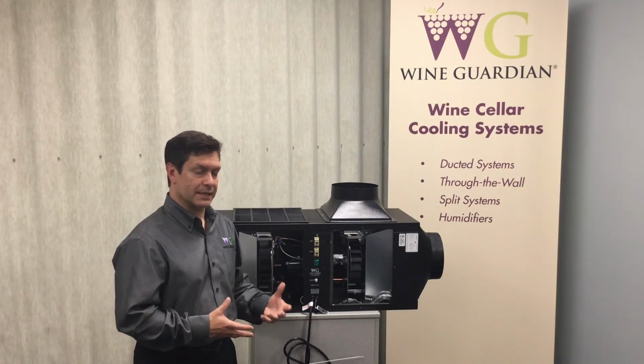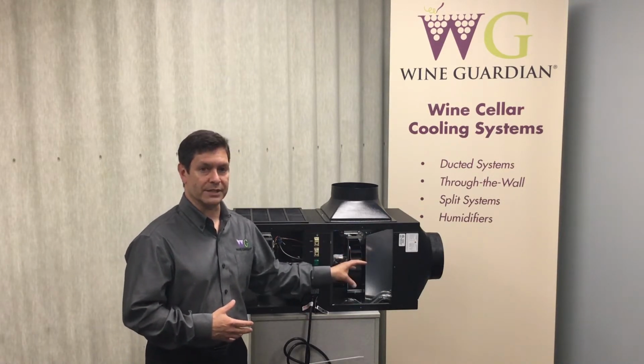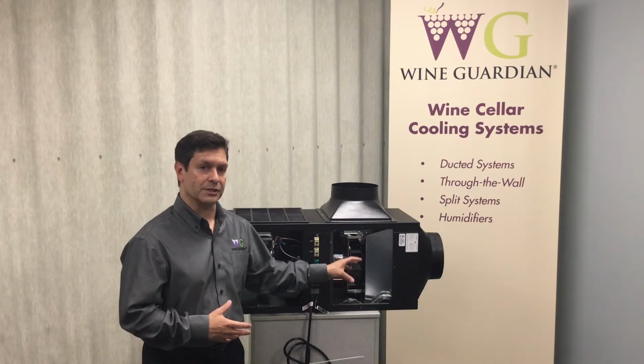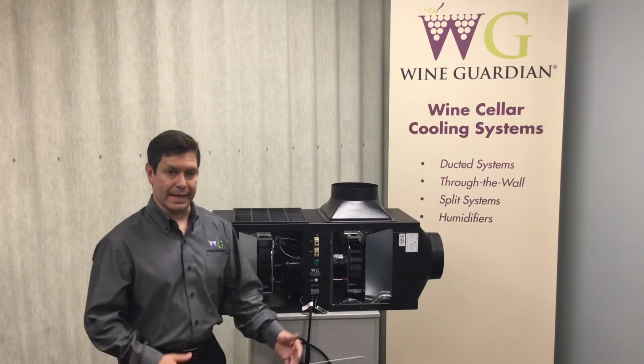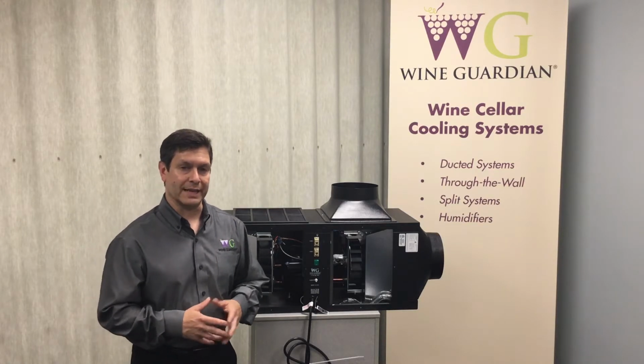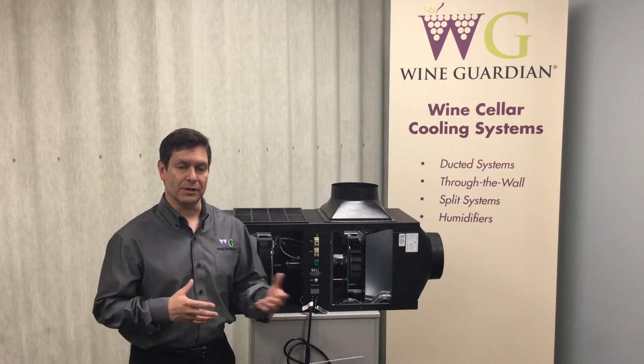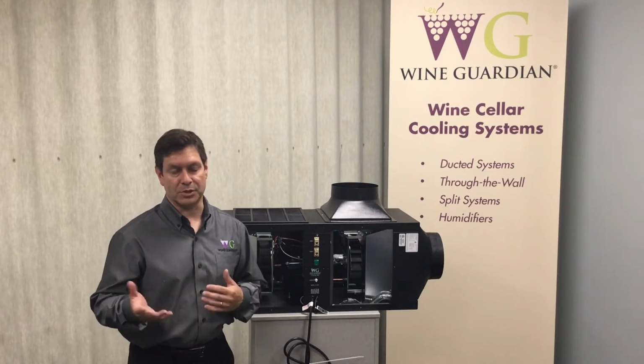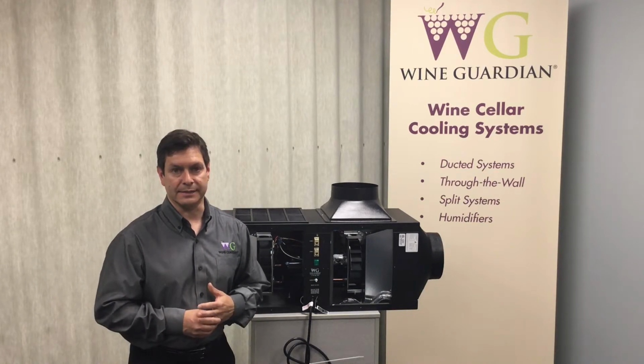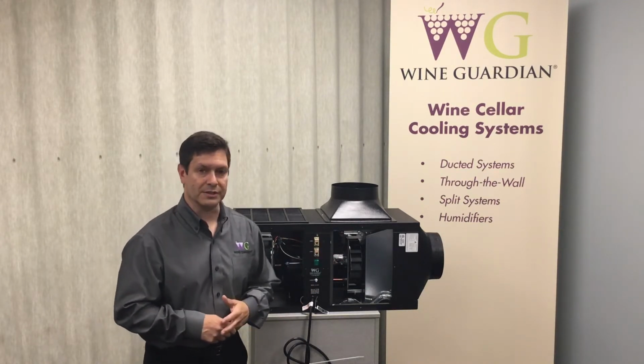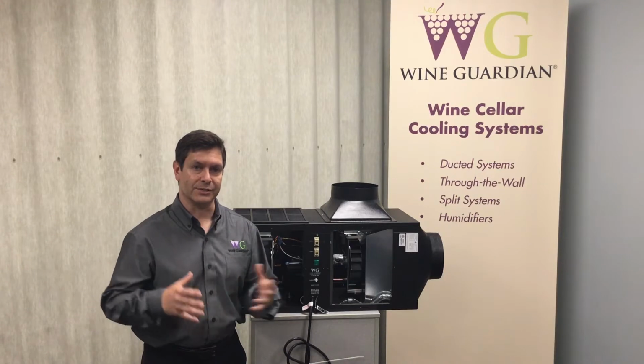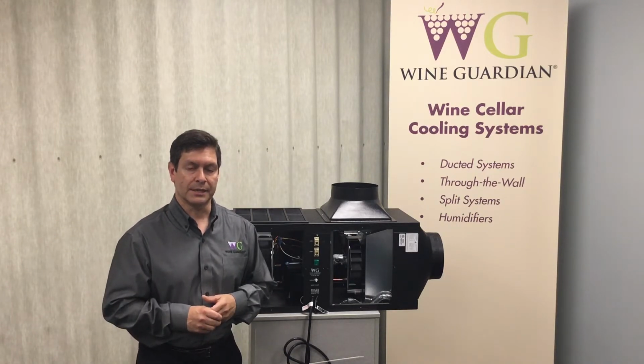So what that does is it prevents the coil from freezing up, a defrost control of the system. That allows us to create that operating range from the low 40s up to the high 60s. Obviously the freezing coil doesn't happen at the higher temperatures, but it does broaden that range of performance.